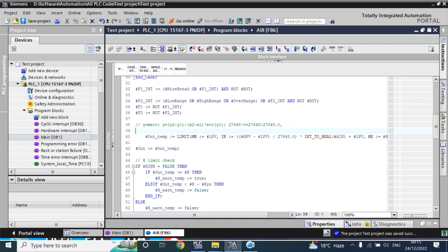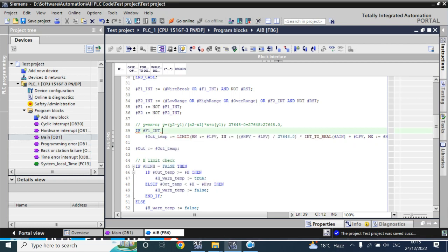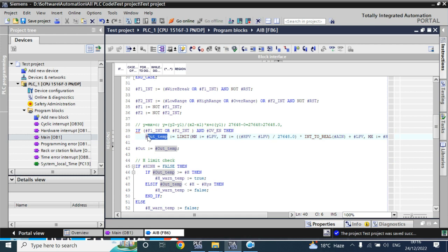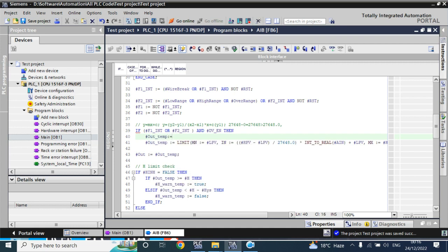These three conditions will be written using IF instructions. First instruction: if F1 internal is ON — meaning a wire break has occurred — or F2 internal is enabled, which happens due to low range, high range, or over range, and the DV enable pin is high, then our temporary output value will be copied from the DV value.